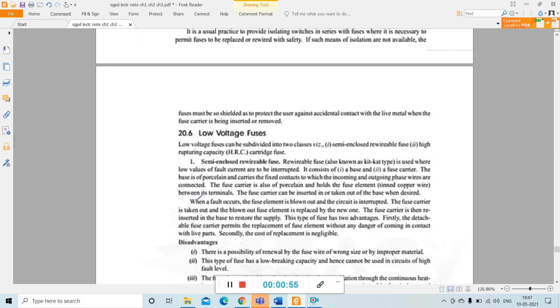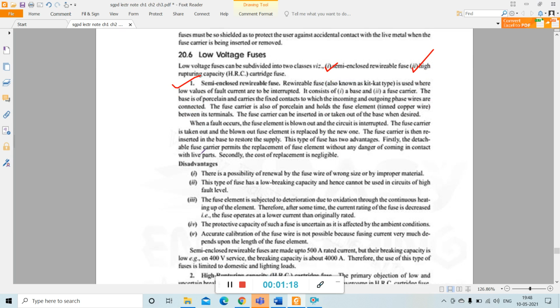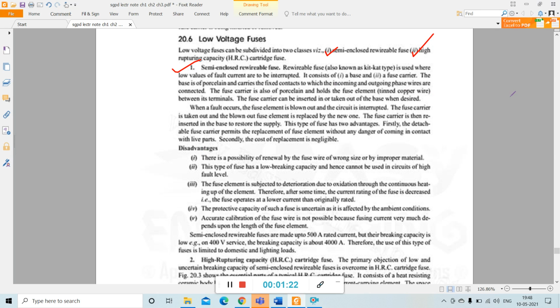First, we will discuss the low voltage fuse. Under low voltage fuse, it is again divided into two types. One is the semi-enclosed rewirable fuse, and the second one is the high rupturing capacity fuse. Okay, so the semi-enclosed rewirable fuse. The rewirable fuse is also known as the KitKat type fuse, and it is used where low values of fault current are to be interrupted. It consists of one base and one fuse carrier. The base is of porcelain and carries the fixed contacts to which the incoming and outgoing phases are connected.